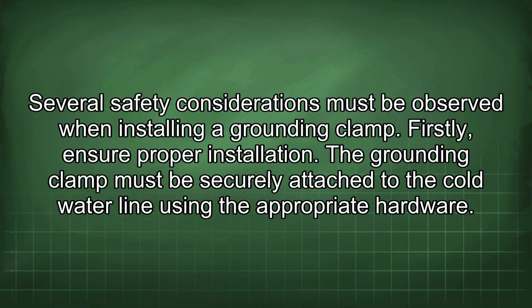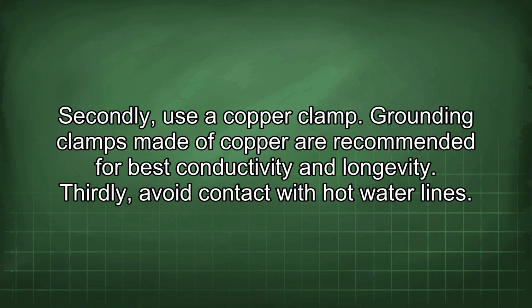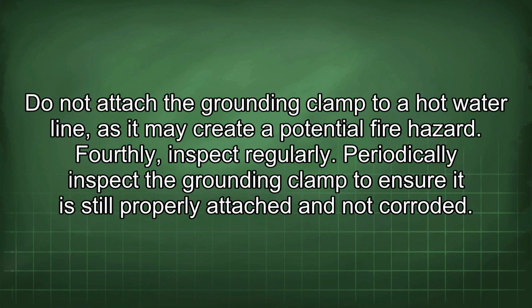Firstly, ensure proper installation. The grounding clamp must be securely attached to the cold water line using the appropriate hardware. Secondly, use a copper clamp. Grounding clamps made of copper are recommended for best conductivity and longevity. Thirdly, avoid contact with hot water lines. Do not attach the grounding clamp to a hot water line, as it may create a potential fire hazard. Fourthly, inspect regularly. Periodically inspect the grounding clamp to ensure it is still properly attached and not corroded.